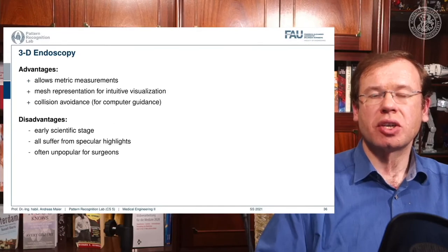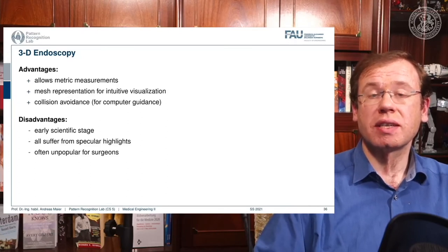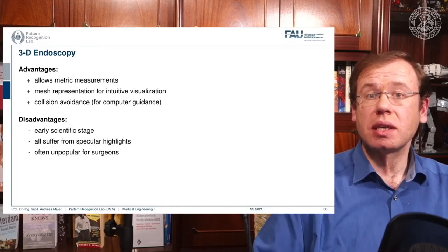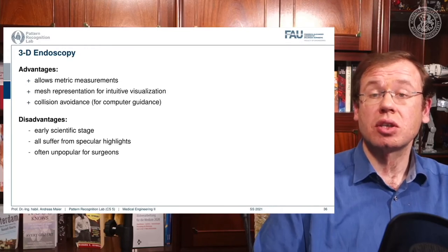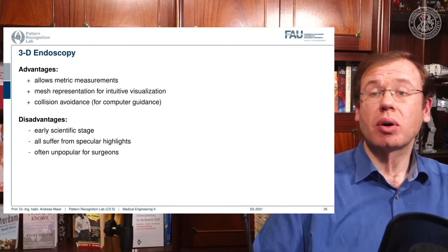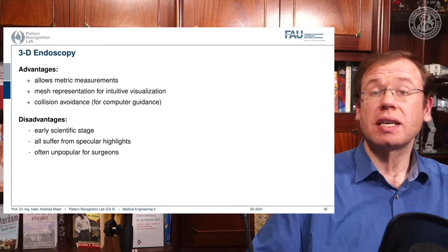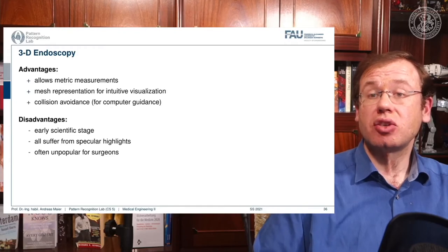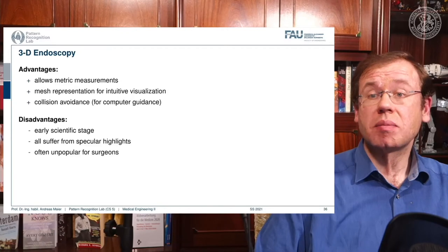An advantage of the 3D endoscope is that it allows metric measurements — because it is calibrated, you can measure distances in millimeters. You also get a mesh representation of the field of view, enabling intuitive visualization where you can change your viewpoint artificially to locations that are physically not accessible. Because the data is metric, you can also avoid collisions, which is very important for computer guidance, especially in keyhole surgeries like brain operations where you don't want to damage certain areas.